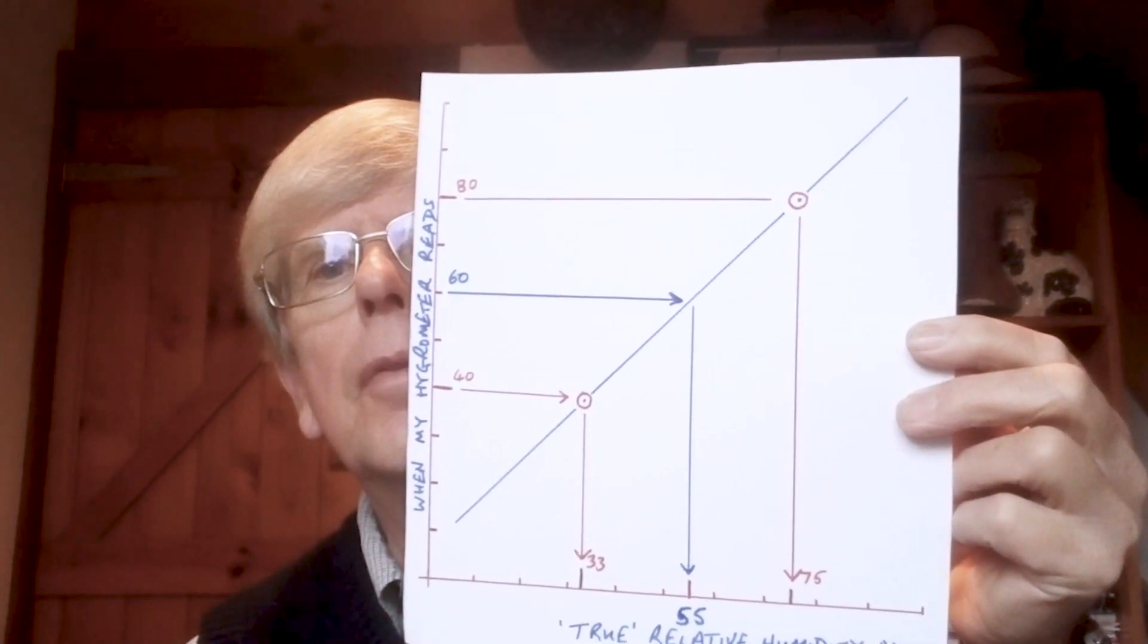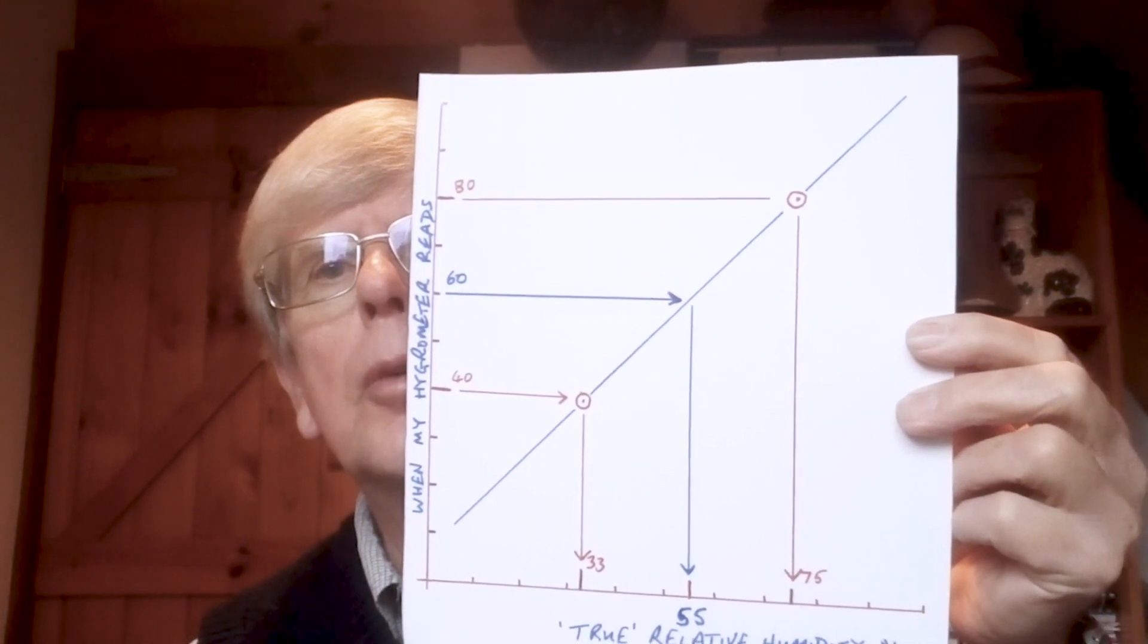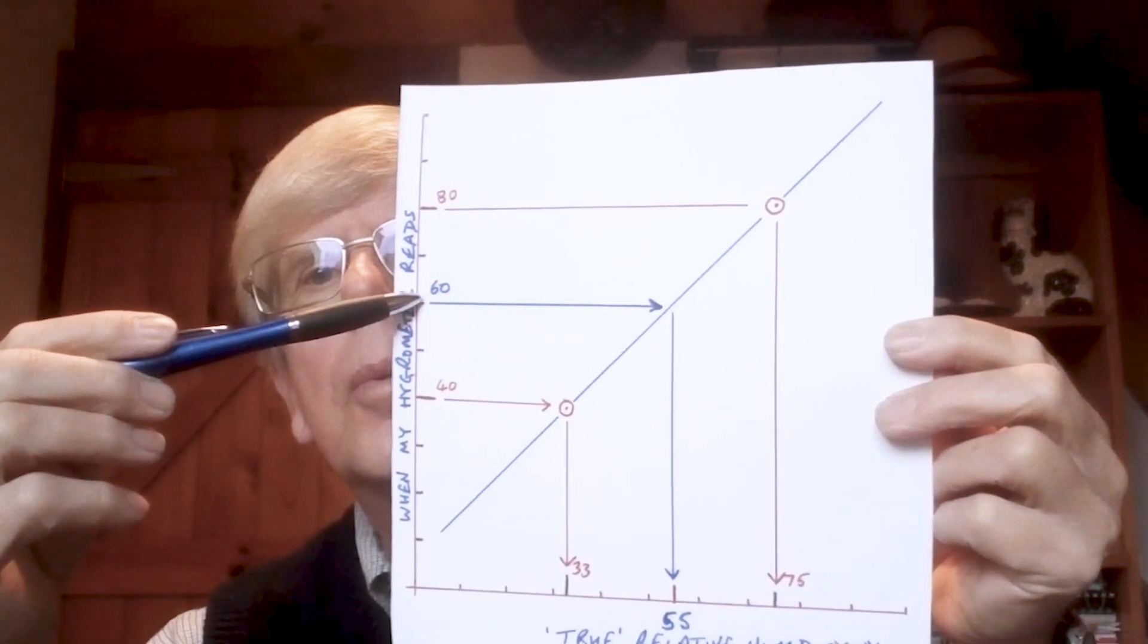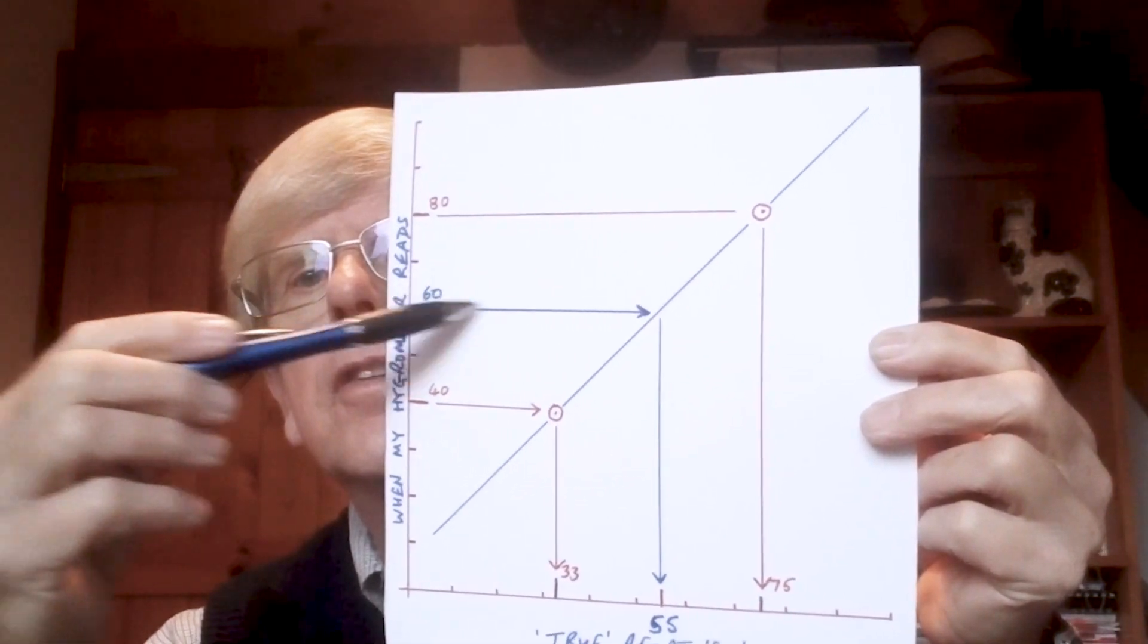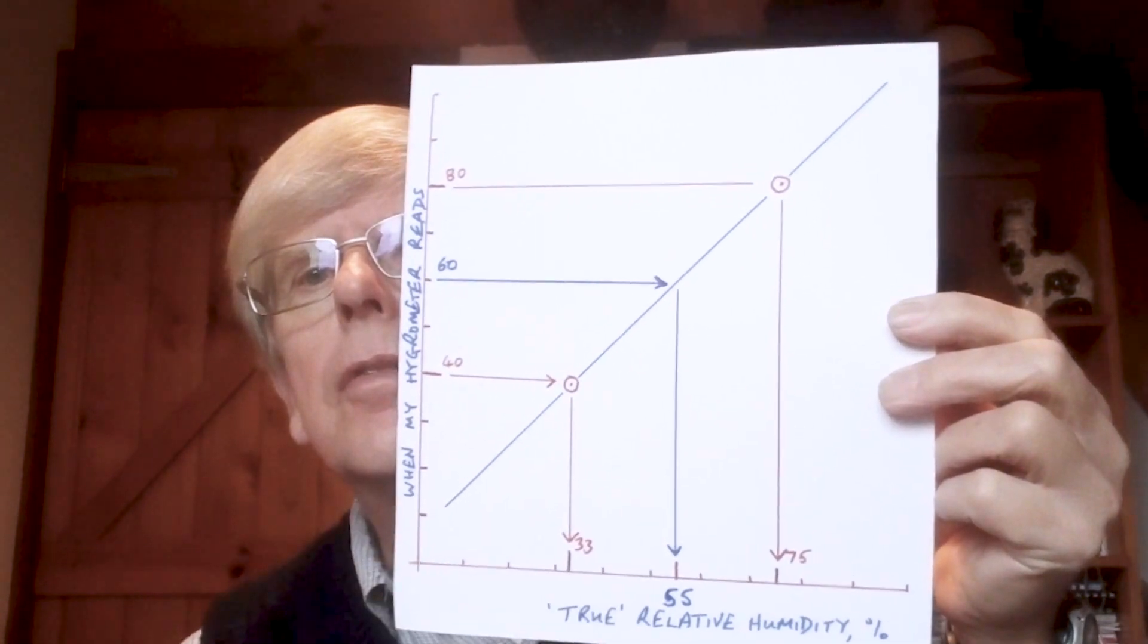So now, you've had to do this because actually you want to read relative humidities round about the 60 mark, 50 mark. So you want to know, well, when my hygrometer reads 60, the true relative humidity is 55.